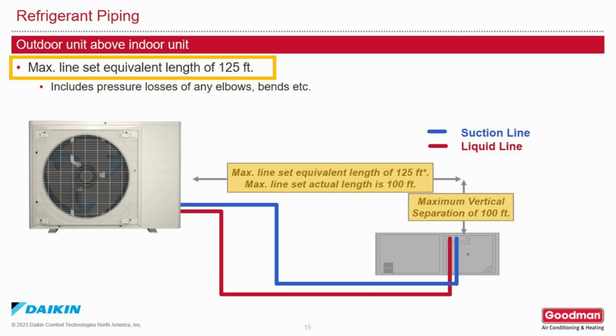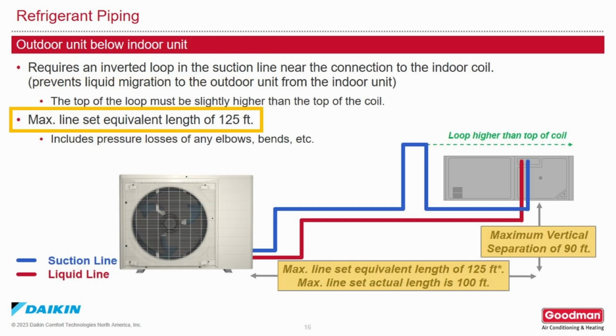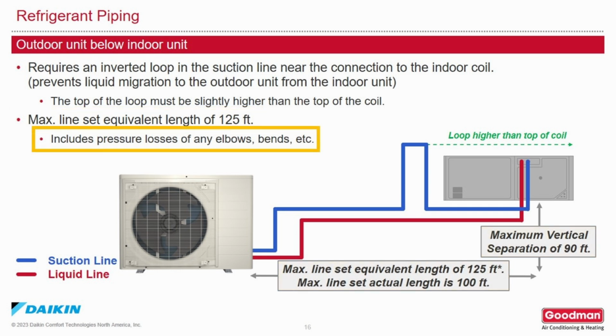Maximum actual line length is 100 feet. The maximum equivalent line length, including fittings, is 125 feet. Maximum vertical separation if the outdoor unit is above the indoor unit is 100 feet. If the outdoor unit is situated lower than the indoor unit, the maximum total line length is 100 feet. The maximum equivalent line length, including fittings, is 125 feet. The maximum vertical separation is 90 feet.